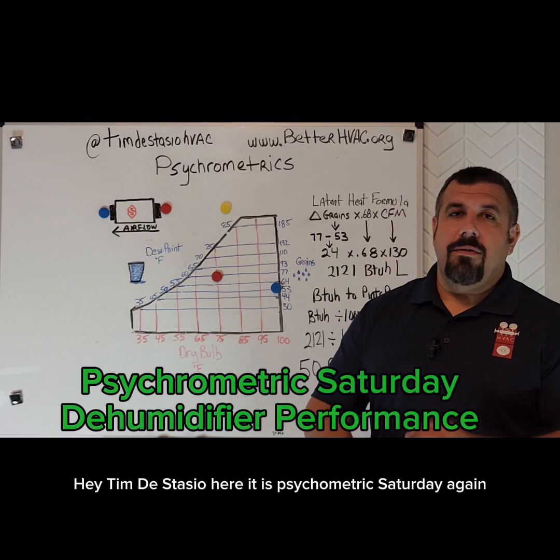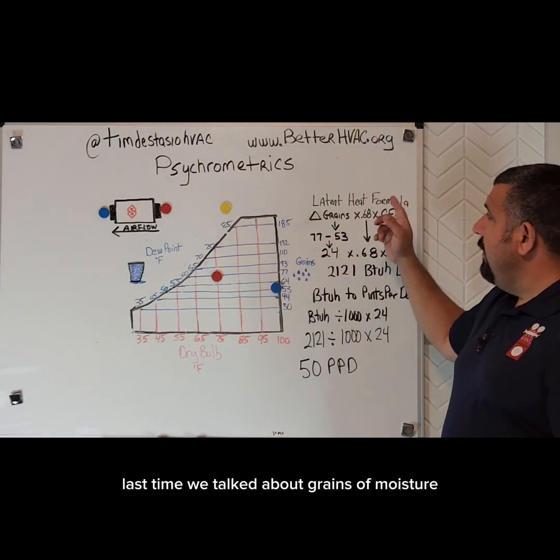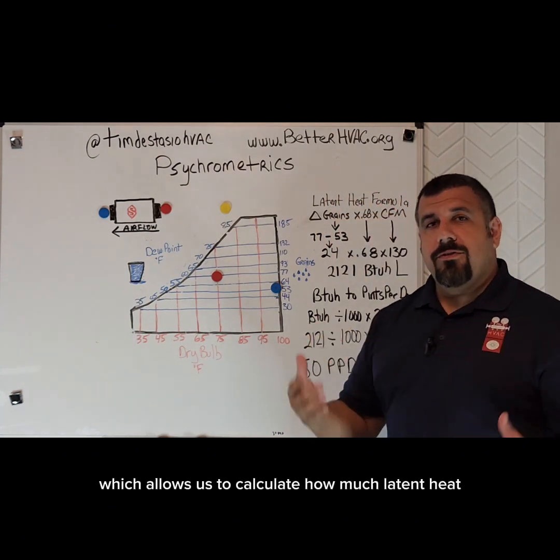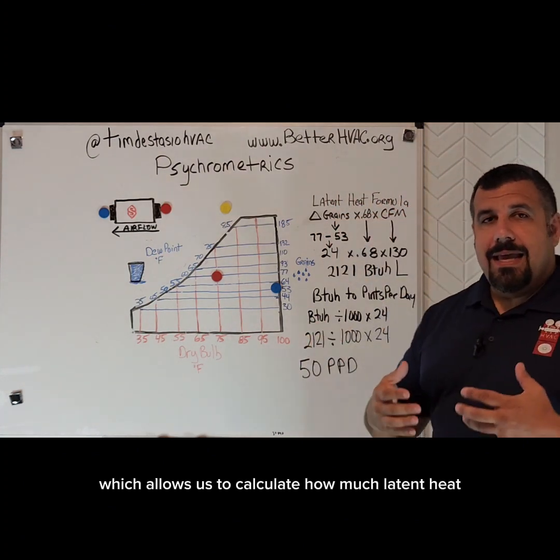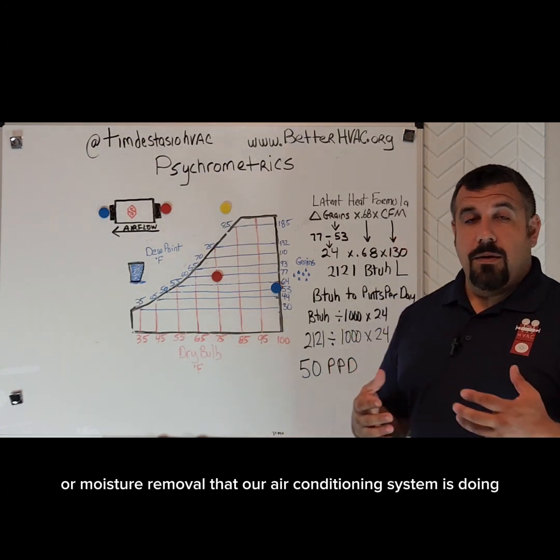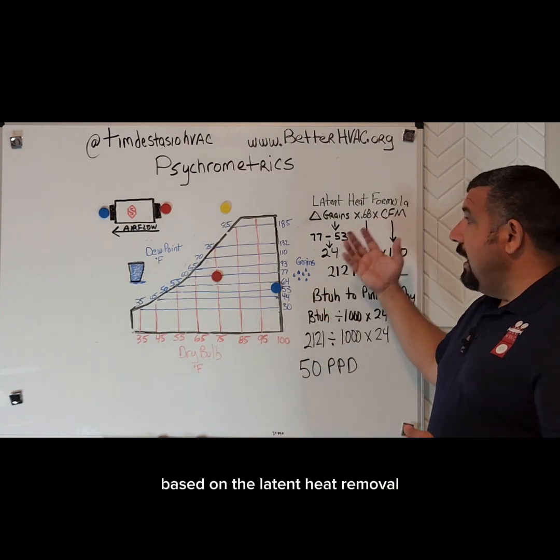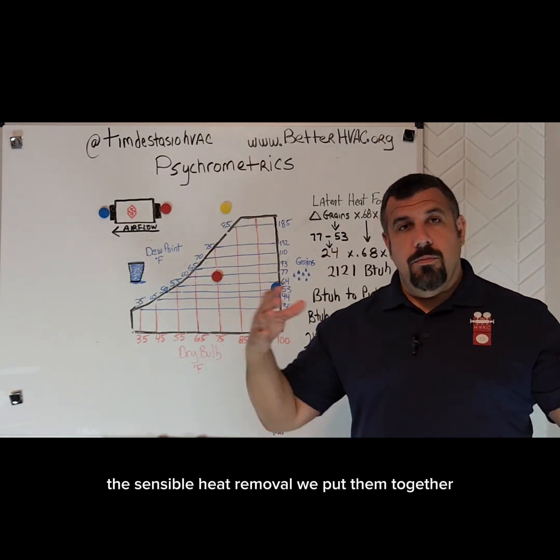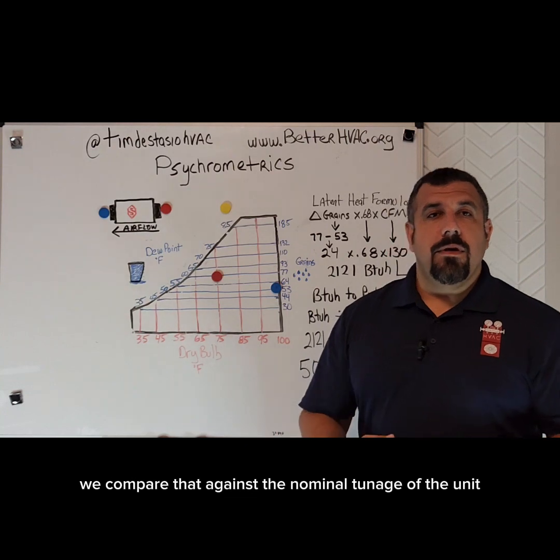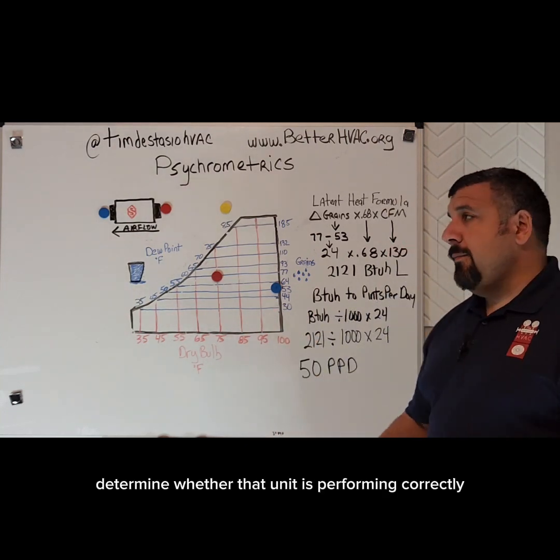Hey, Tim DeStasio here. It is Psychrometric Saturday again. Last time we talked about grains of moisture and the latent heat formula, which allows us to calculate how much latent heat or moisture removal our air conditioning system is doing. We can tell a lot about how a system performs based on the latent heat removal and the sensible heat removal. We put them together — that's total heat — and compare that against the nominal tonnage of the unit to determine whether it is performing correctly.